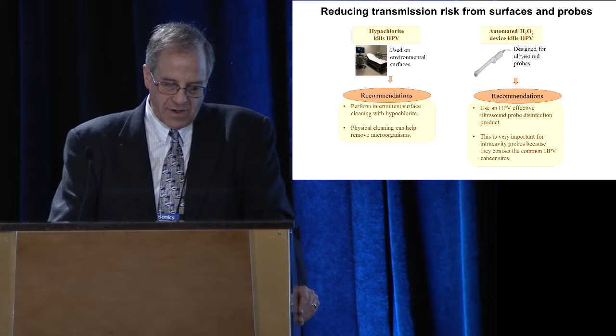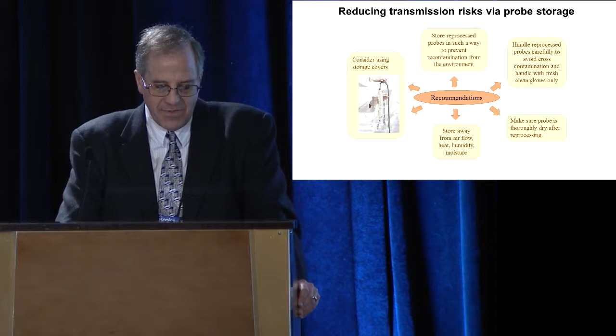So, reducing transmission risk via probe storage, we heard a little bit of this already. Consider using storage covers. Store reprocessed probes carefully, because remember, if 20% of people have it on their fingertips, and somebody comes and grabs the probe, they've just put it back onto the probe. Store the reprocessed probe in such a way to prevent recontamination from the environment. Handle reprocessed probes carefully to avoid cross-contamination and handle with fresh, clean gloves only. Make sure the probe is thoroughly dry after reprocessing, and store away from airflow, heat, humidity, and moisture.